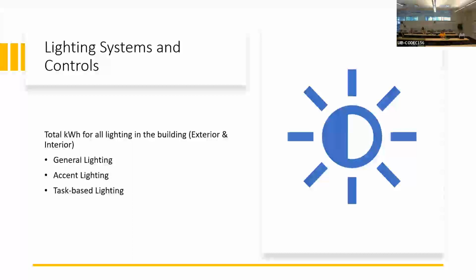Something to keep in mind when calculating kilowatt hours or lighting power density, trying to quantify how much is being used by the lighting system, is that it's going to be different than the code standard applied, because you have allowances, exceptions, and so on. But for the audit and energy assessment, you're still consuming that power, it still takes power to turn on those accent lights, even though they didn't have to be considered for code or contract purposes. So keep in mind those numbers are probably going to be different. And if you apply the allowance or exemptions and it comes into line, that's good, it means we're where we're supposed to be.